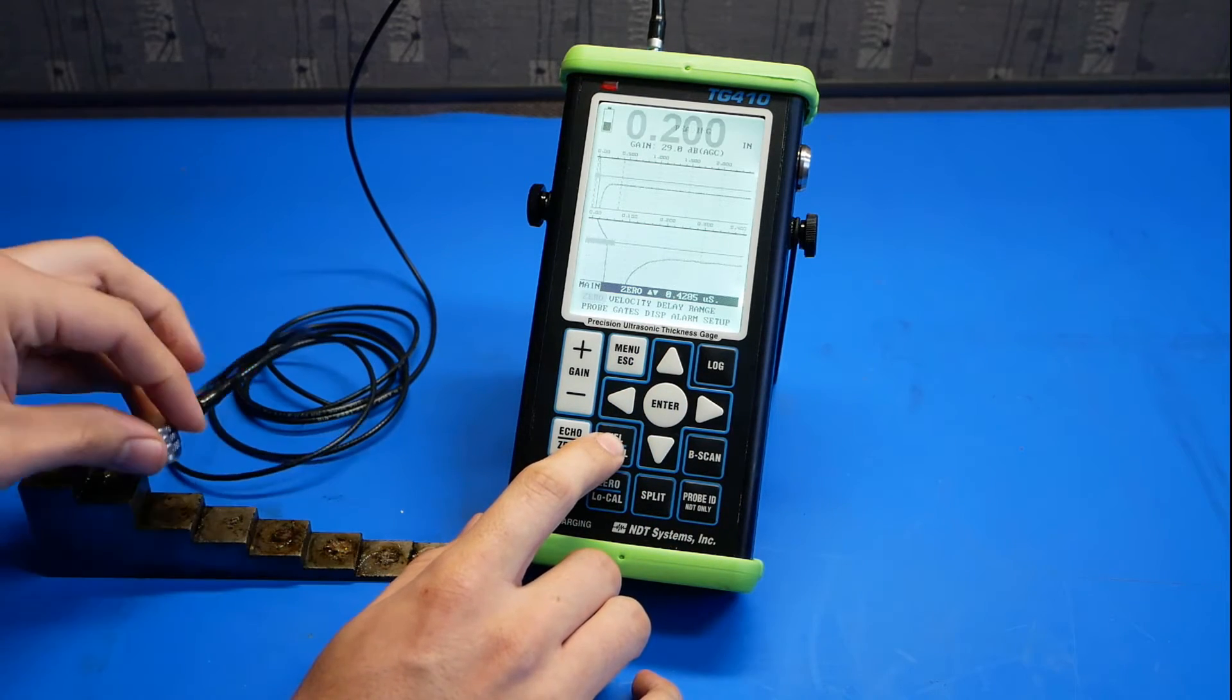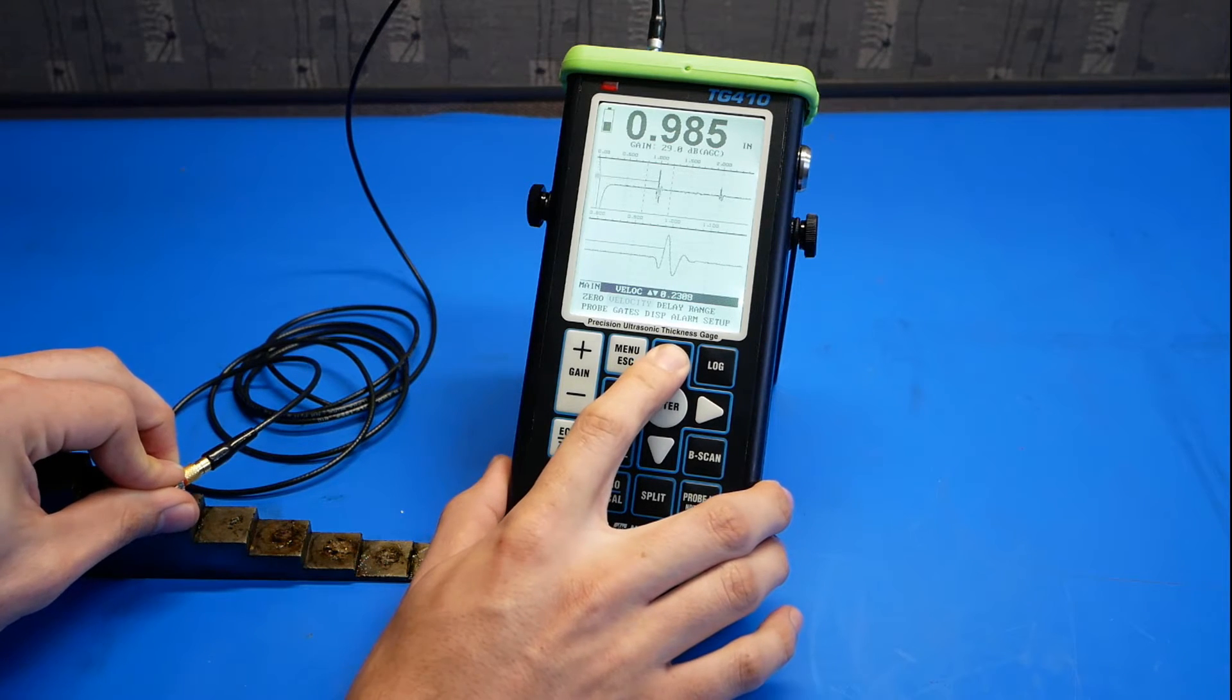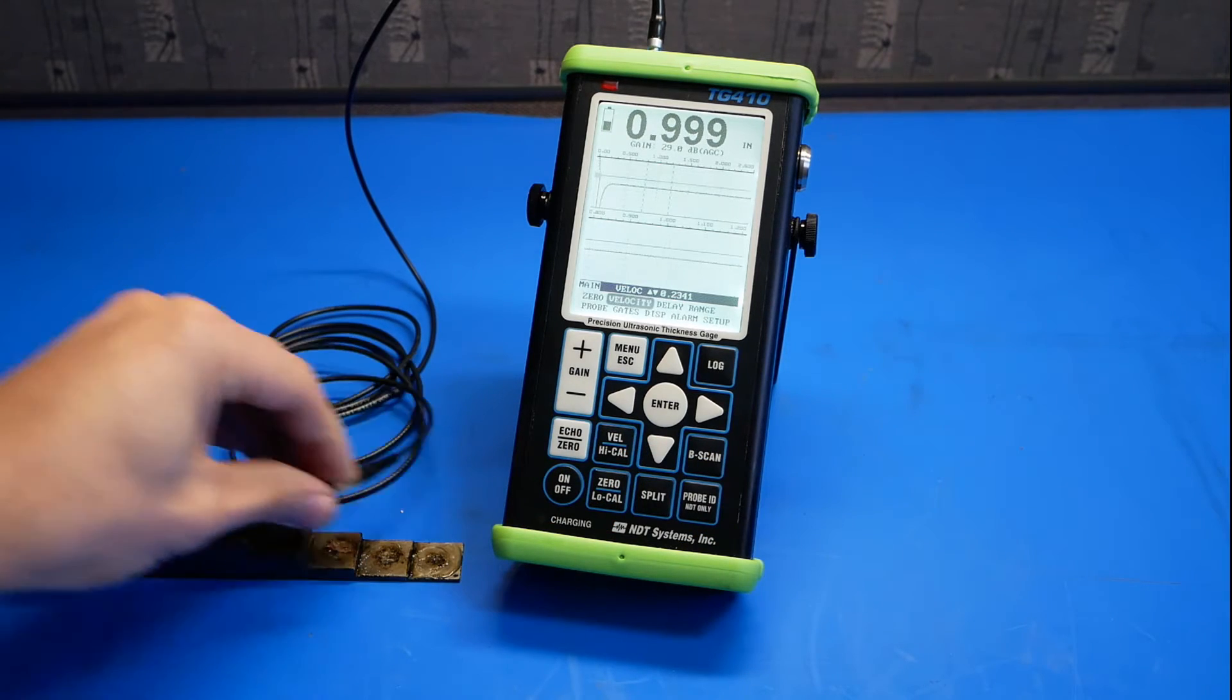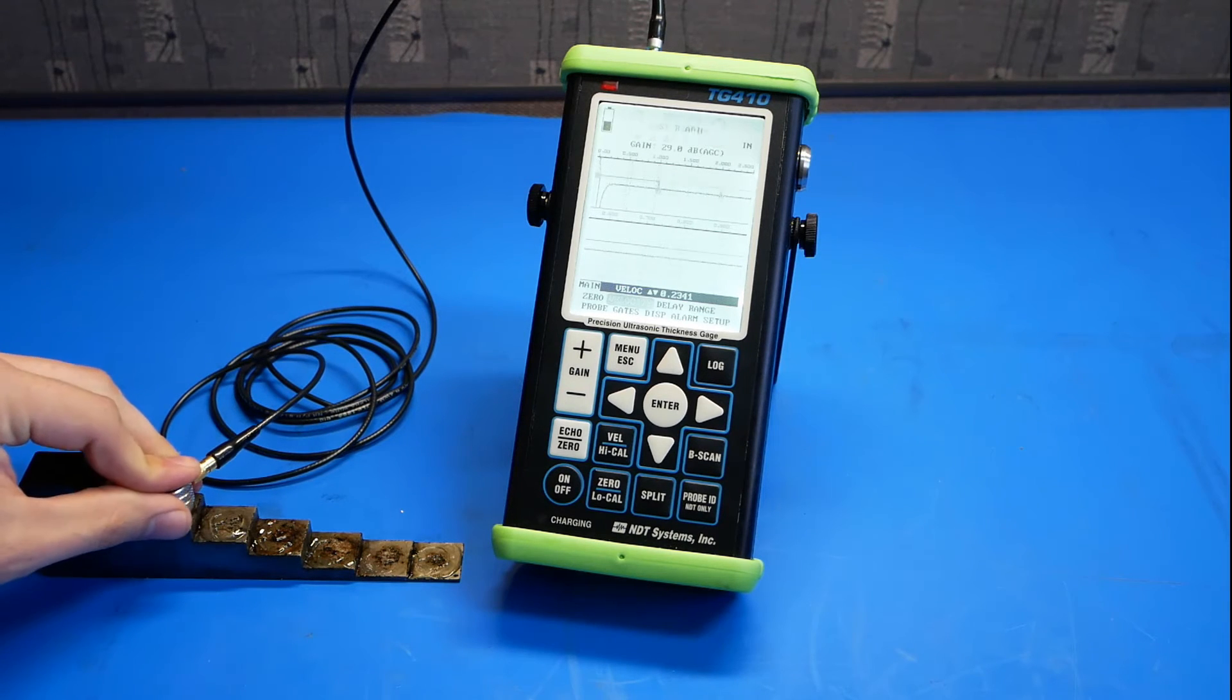Next, go to velocity high cal and couple to a region of high thickness, in this case 1 inch. And increase the velocity until we get our desired reading. Now, if we go and couple along various parts of the cal block, may need more couplet over time as it dissipates, we can see that all the readings are within tolerance.